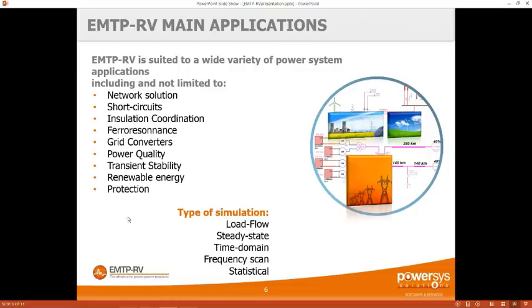Now let's talk about EMTP-RV itself. EMTP-RV is a transient software. A transient software starts with the same equations as a stability package — for example, for the inductance, the voltage equals the derivative of the flux. But instead of going to the Laplace domain, a transient software integrates this equation step by step.